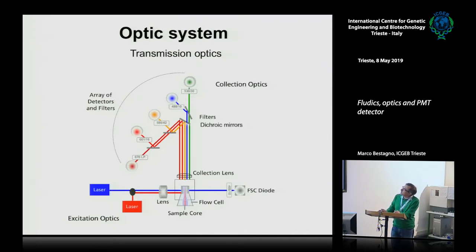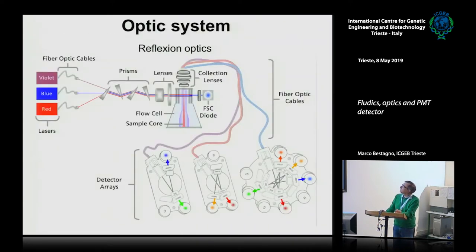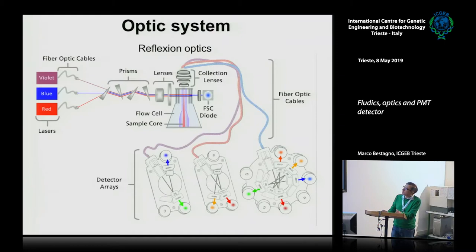In a transmission optics system, the last detector receives light that has crossed multiple filters, resulting in dispersion and reduction of signal intensity. This system can be used when the number of detectors is small, but with more complex instruments having several detectors, there is a progressive reduction of signal. Therefore, more complex instruments use reflection optics. In this case, light is drawn to the interrogation point by means of optical fibers to reduce light dispersion, and then collected by lenses and drawn by fiber optics to the detector array.